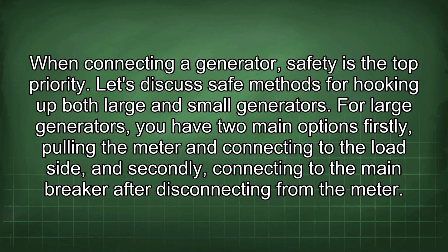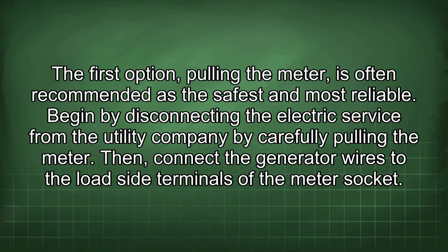When connecting a generator, safety is the top priority. Let's discuss safe methods for hooking up both large and small generators. For large generators, you have two main options: firstly, pulling the meter and connecting to the load side, and secondly, connecting to the main breaker after disconnecting from the meter. The first option, pulling the meter, is often recommended as the safest and most reliable.